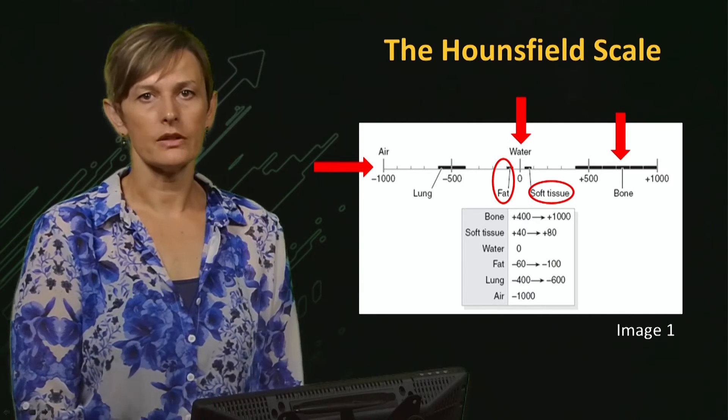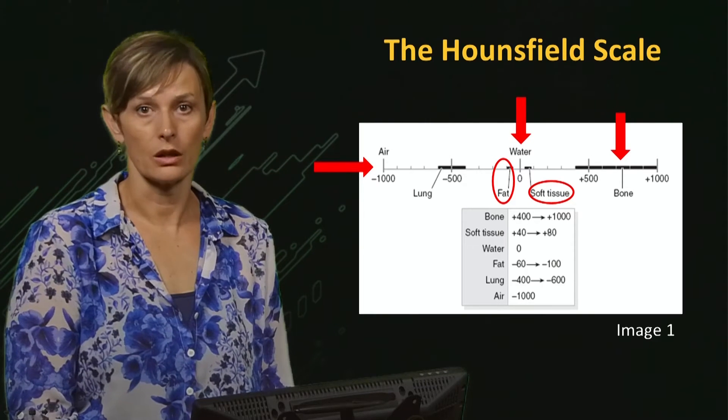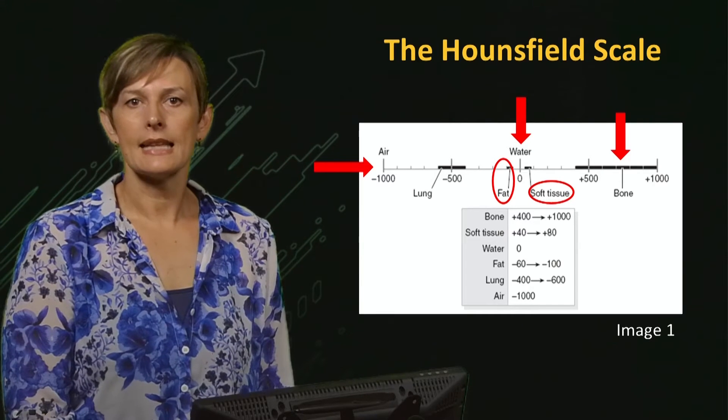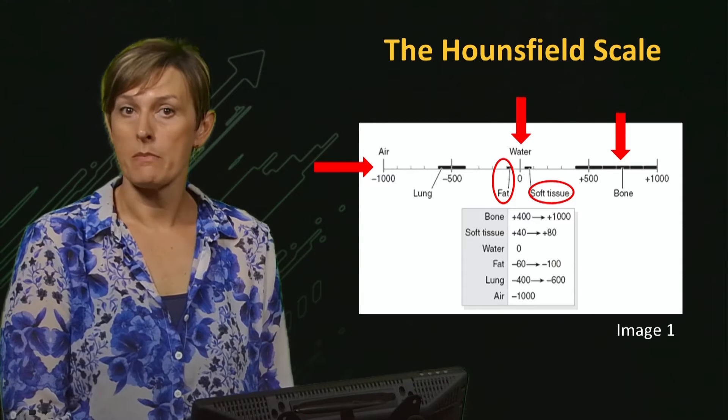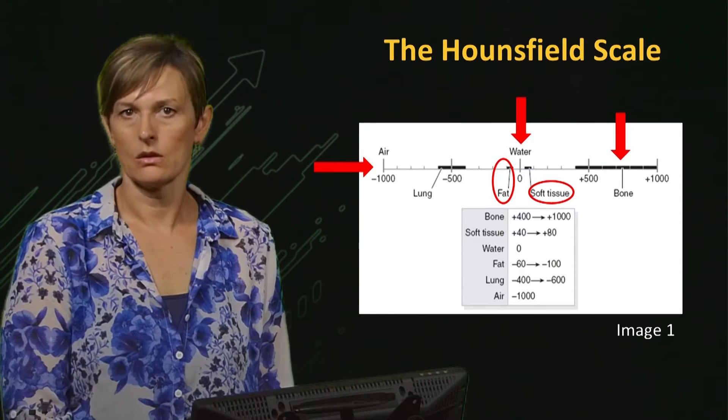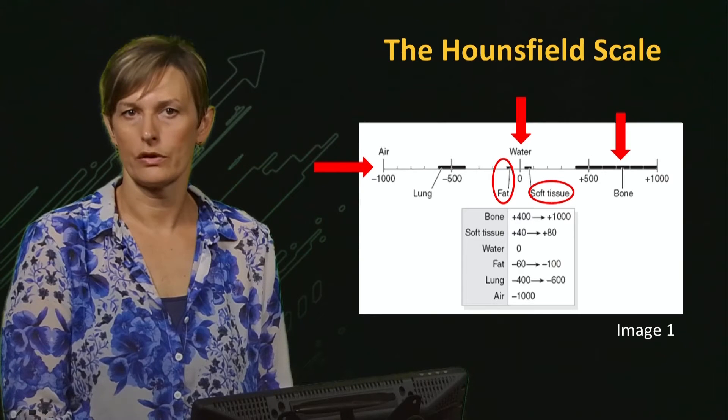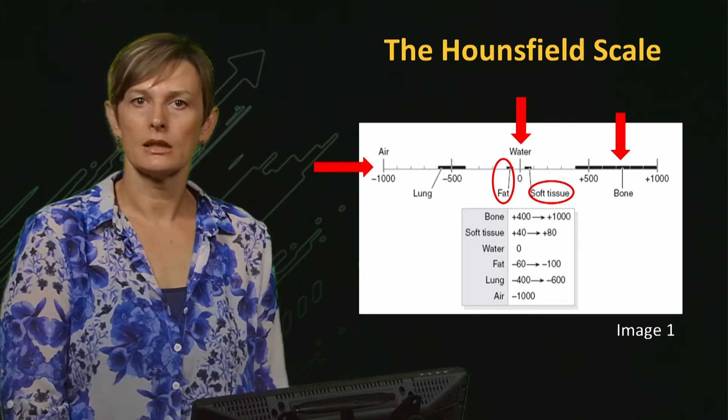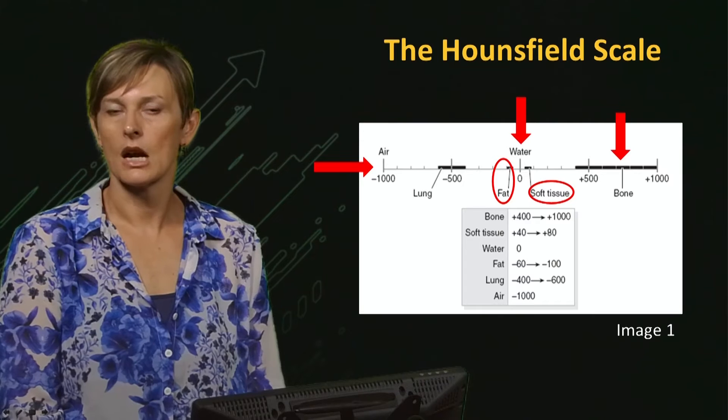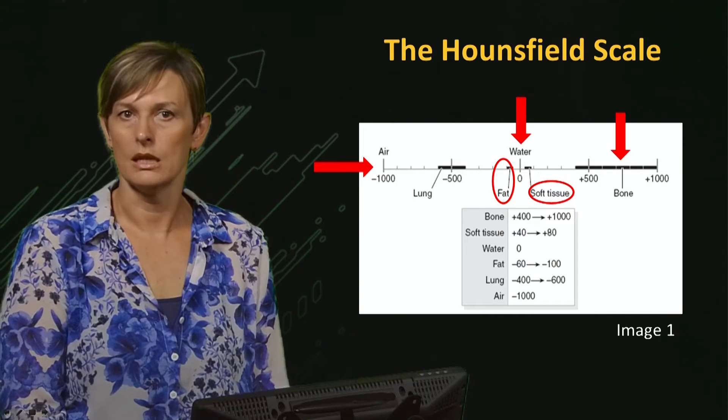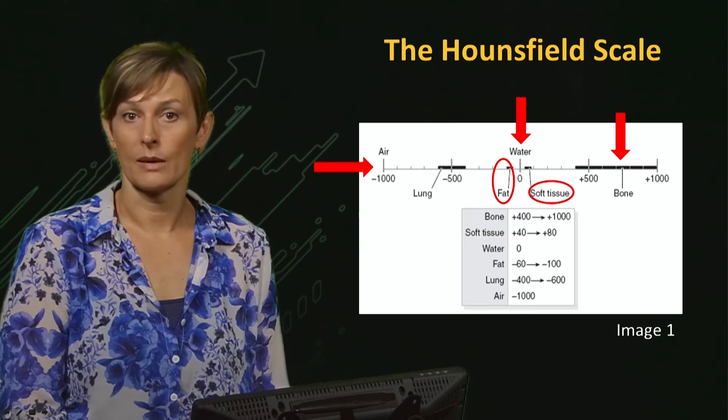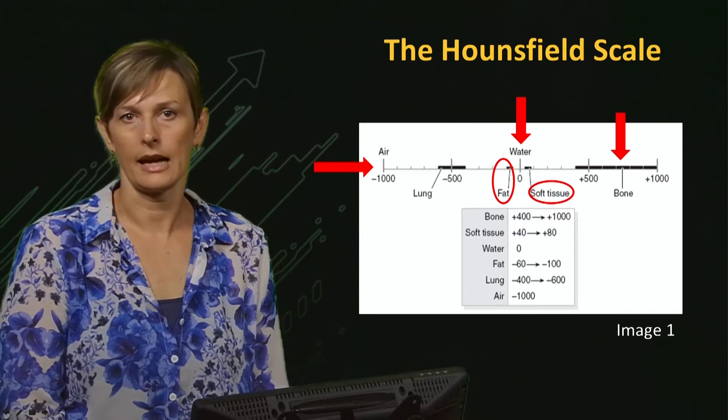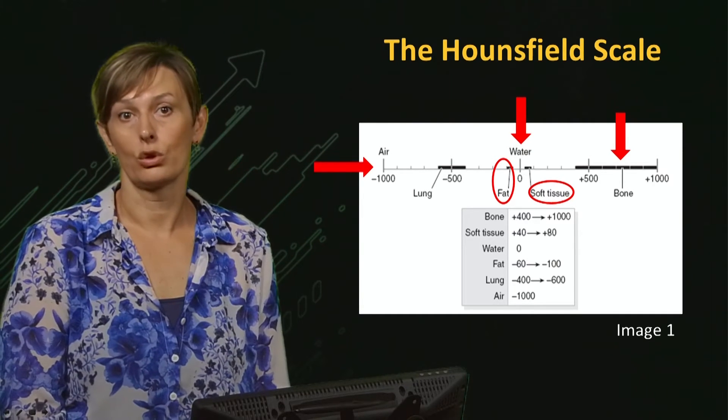The contrast between soft tissue with HU value from zero to hundred often challenges the resolution of CT scanners. Let's take an example of gray and white matter in the brain. The gray matter, which has a pinkish gray color, contains nerve cell bodies, whereas the white matter is made of connection axons transporting information between different parts of the brain. Both are soft tissue in the brain and the difference between the two is approximately five to ten HU. So the contrast resolution of the CT scanners need to be high to pick up such a small difference.